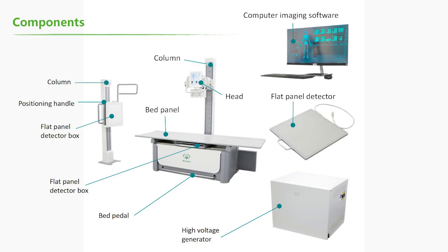You can see a pedal at the bottom of the machine. It works like the switch. If you don't touch it, the bed is locked. But if you step on it, the bed can be adjusted to acquire the best image. On the right side of the slide, you can see the flat panel detector. It should be put in the flat panel detector box, either under the bed or on the chest stand.